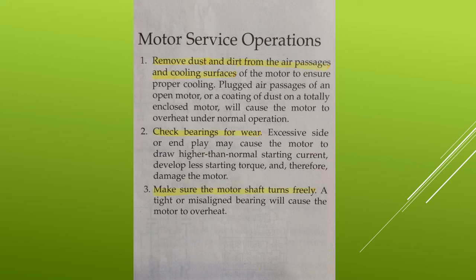Step one is to remove dust and dirt from the air passages and cooling surfaces of the motor to ensure proper cooling. Plugged air passages of an open motor or a coating of dust on a totally enclosed motor will cause the motor to overheat under normal operation. Step two, check bearings for wear. Excessive side or end play may cause the motor to draw higher than normal starting current, to develop less starting torque, and therefore damage the motor.